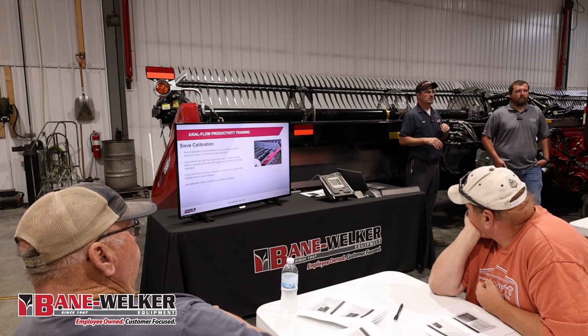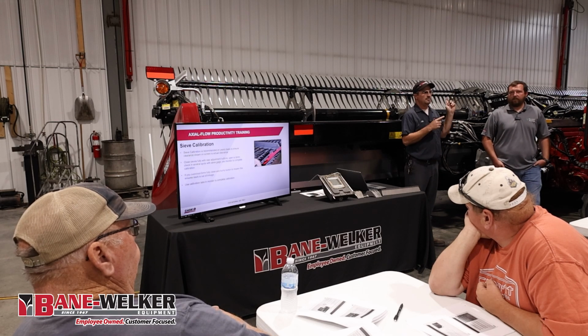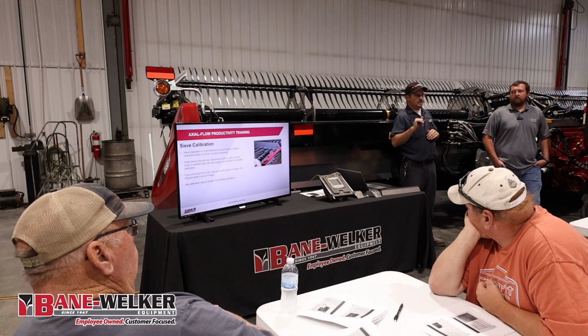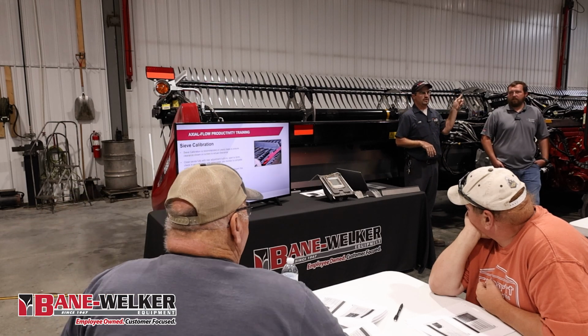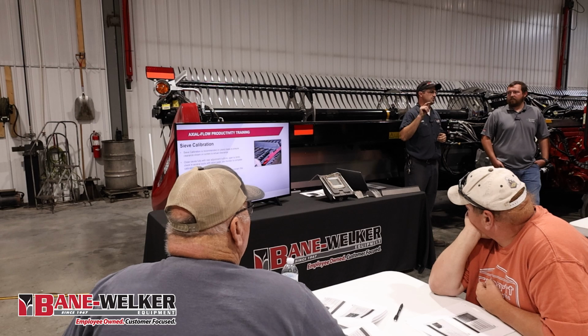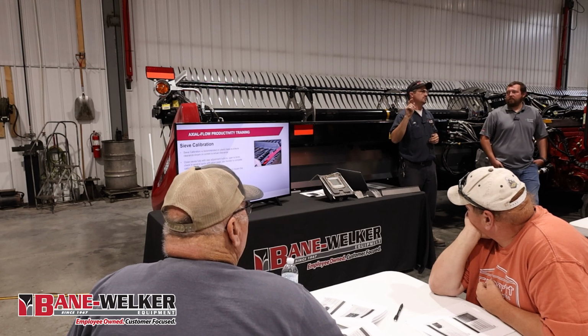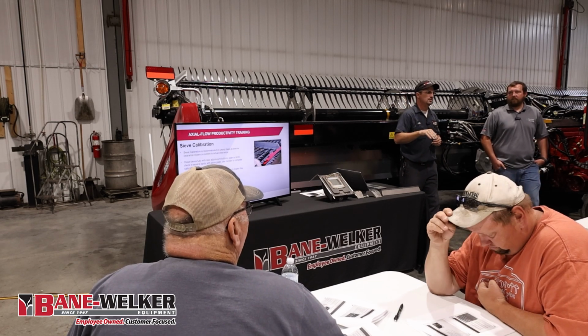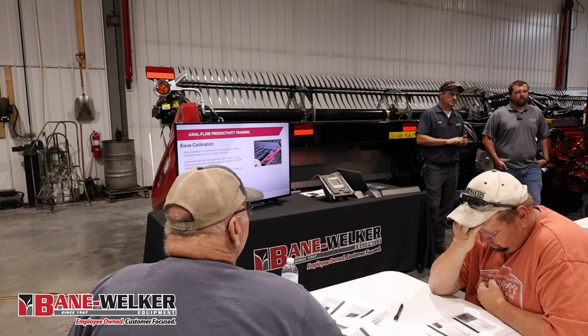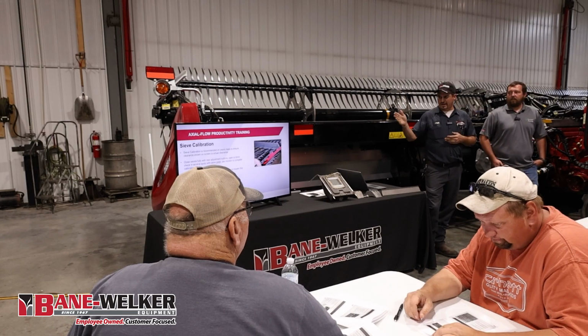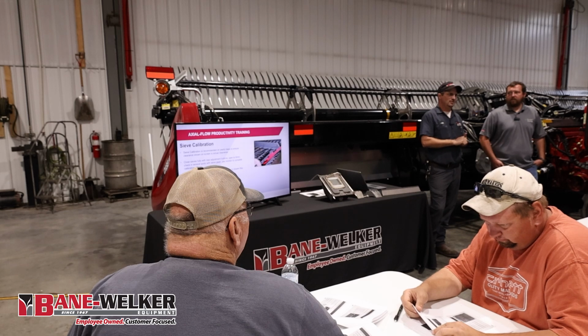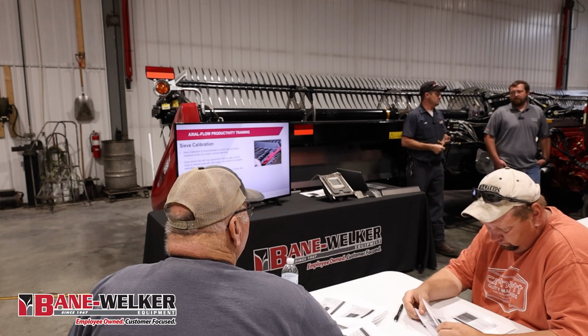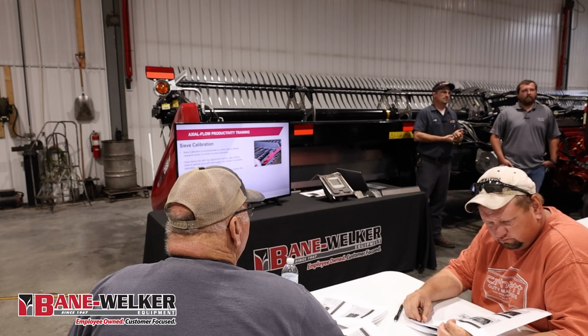That's the critical part, but you can save yourself a lot of leg work and climbing up and down if we have all those set ahead of time. Then you can just go through all three of those in your display. Say yes, I'm just confirming: okay, I'm at 1/4 inch. Okay, I'm at 1/4 inch. Okay, I'm at 1/4 inch. And then you're done. That calibration's done, and unless you've had mechanical damage on that sieve, or we've changed a sieve, that's done. You don't have to do it again.